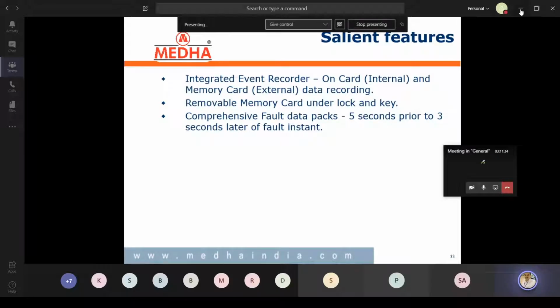Comprehensive fault data packs 5 seconds prior and 3 seconds later than the fault instant. So in general, the fault second, the fault instant, 5 seconds prior and 3 seconds later. In total, 10 records we are able to record for 9 seconds of data for identifying the exact root cause of the fault during analysis.